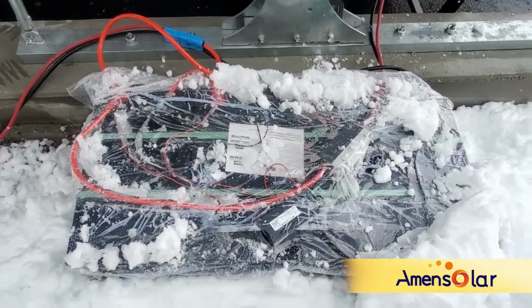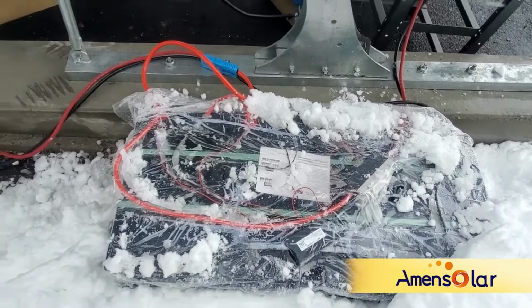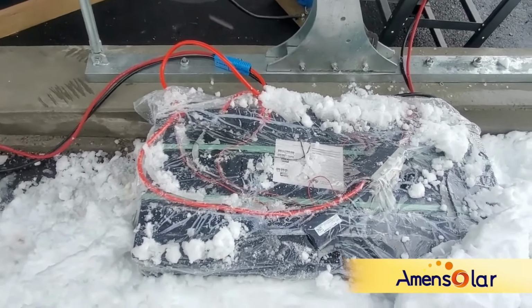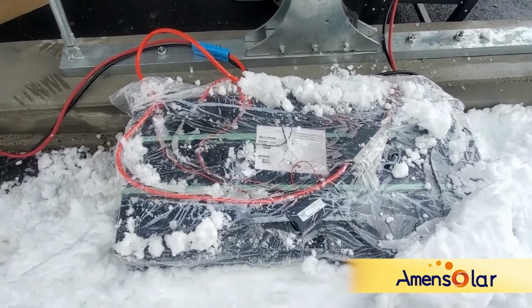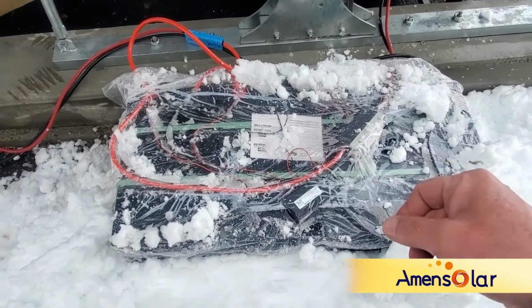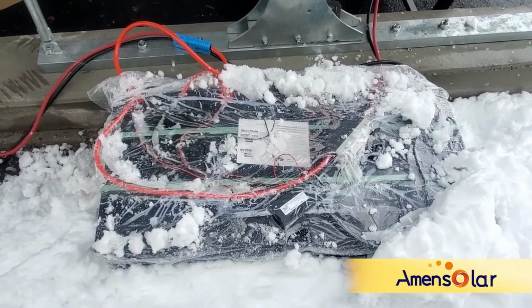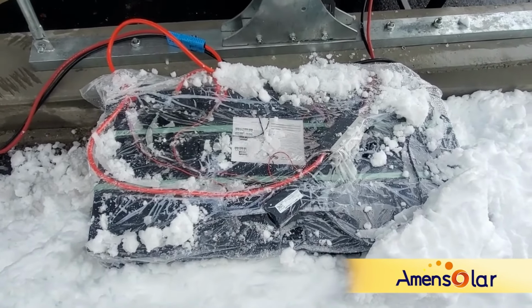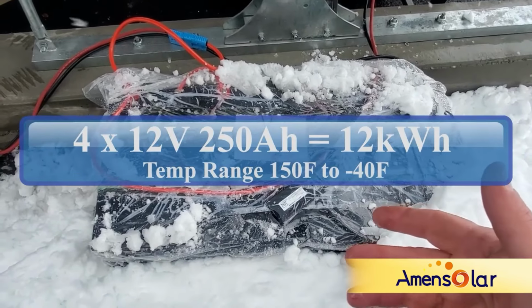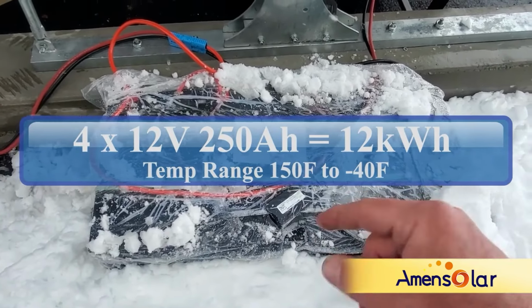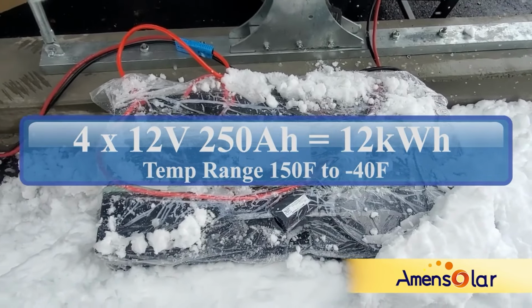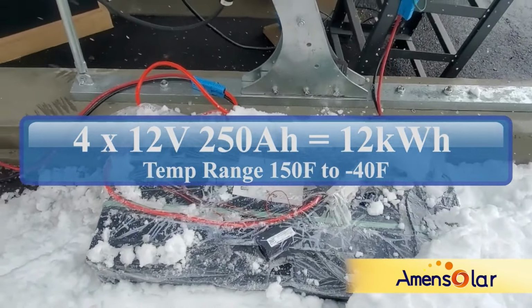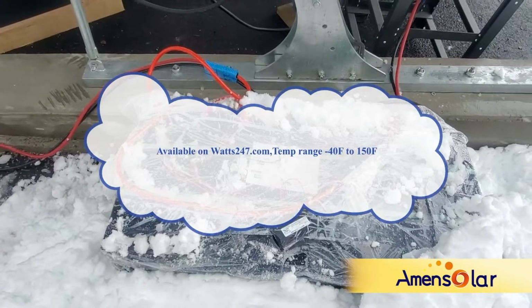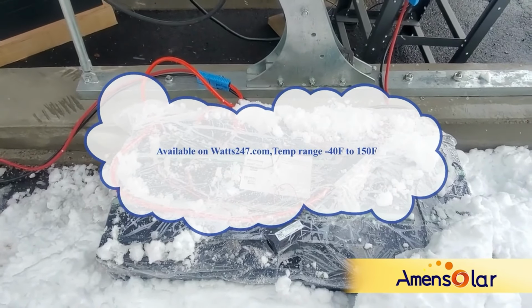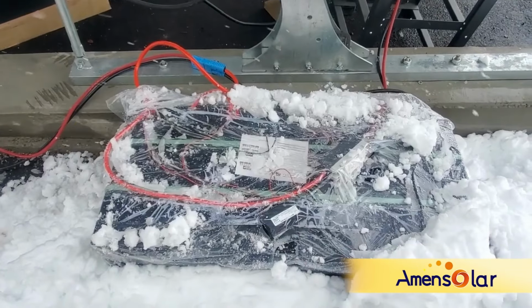There's the equalizer over there. If you exceed, let's say 100 amps on a single battery in that rack, the batteries will cut out. Now these analog batteries will give you everything they have: 100 amps, 200 amps, 300 amps. So it's good, in my experience, to parallel these silica gel batteries with your lithium batteries. They have exactly the same voltage range as a 16S battery, which most of these lithium batteries are. There are a few 15S and 14S batteries out there which have a lower charging voltage, so these are perfectly compatible with a 16S battery.